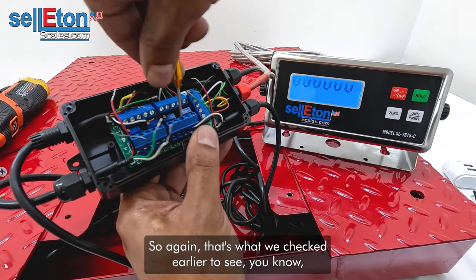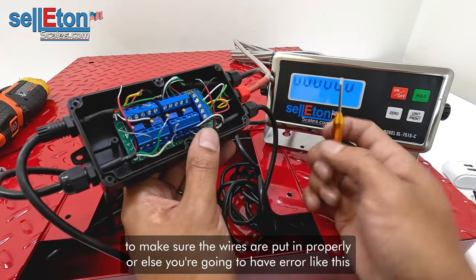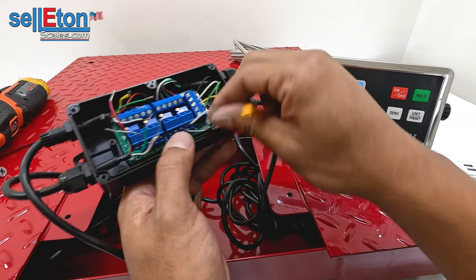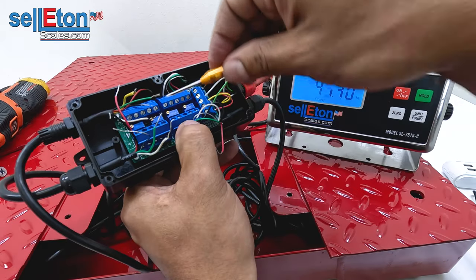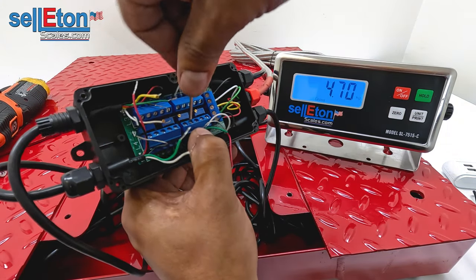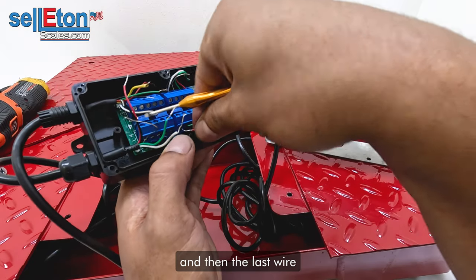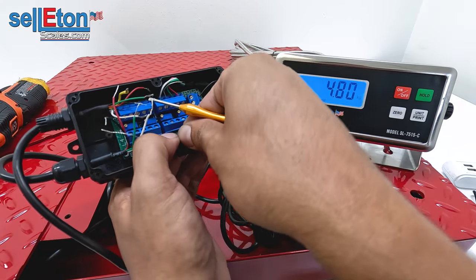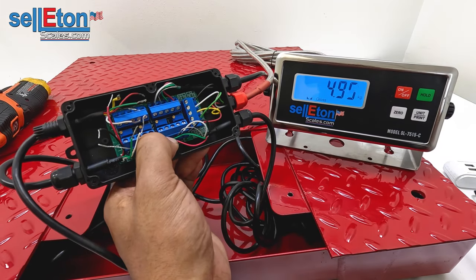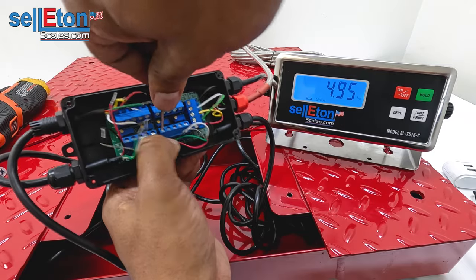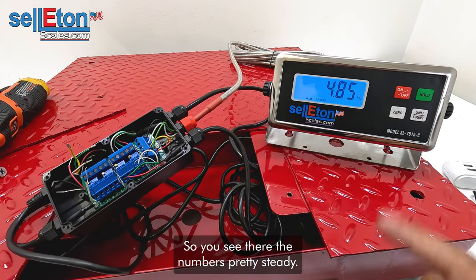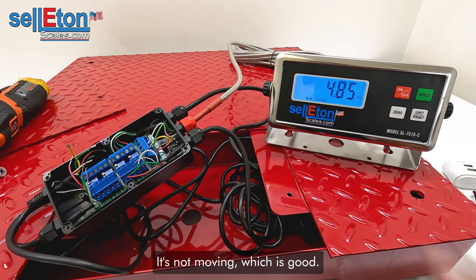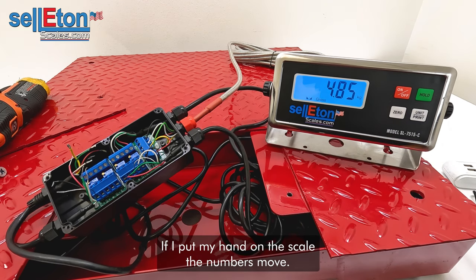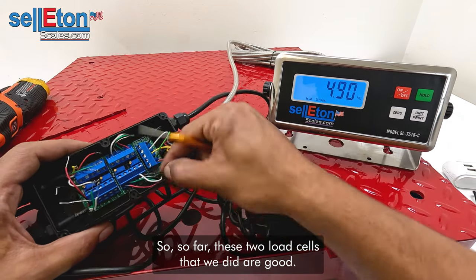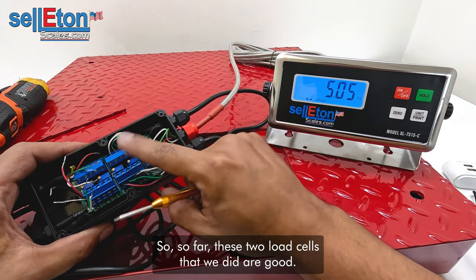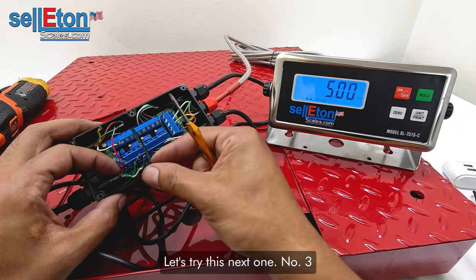Again, that's what we checked earlier, to make sure the wires are put in properly, or else you're gonna have an error like this. And then the last wire is red. Good. Okay, so you see there, the number is not moving, which is good. If I put my hand on the scale, the numbers move. So that's a good load cell as well. So far, these two load cells that we did are good. Let's try this next one, number three.